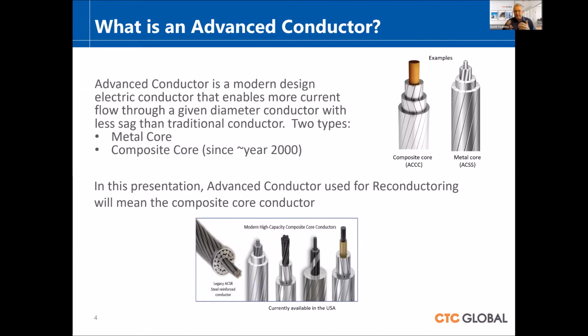So what's an advanced conductor we're talking about here? An advanced conductor is just a modern design conductor that enables more current to flow over the same diameter conductor with less sag than the traditional conductor. And there are metal core type advanced conductors, and there are carbon or carbon composite core conductors as well. In this presentation, I'm going to talk about advanced conductors used for reconductoring, and I'm going to always be referring to this composite or carbon composite type advanced conductor. And I've shown a little picture there of at least 4 advanced conductors using this composite core that are available in the US.